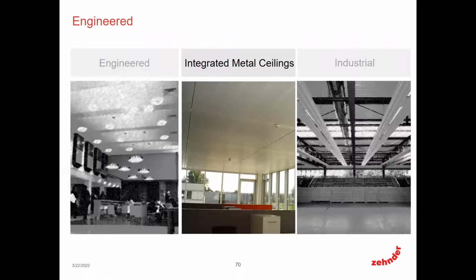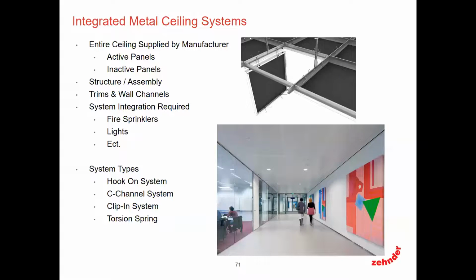Now, everything we've talked about is going to apply. I'm just going to take it literally a step further into what our industry calls either integrated metal ceilings or full metal ceilings. The only difference between what we talked about thus far and this is that instead of the radiant manufacturer just supplying the panels, the hanger kits, and the hoses, now the manufacturer takes responsibility for everything, meaning the entire ceiling. So now we're doing the inactive, the active, the perimeter trim, the lighting integration, the cutouts, all of that gets incorporated into our scope.